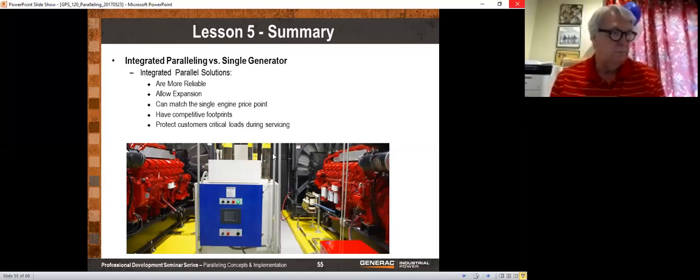Okay, last question here. Is there a minimum load percentage that generators need to be operating at? And does that often become an issue when paralleling? Yeah, it's never an issue when paralleling. Generators, all they do is sync to the voltage, and then once they close, they share the load.